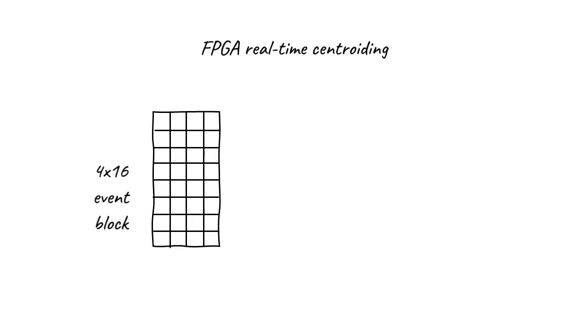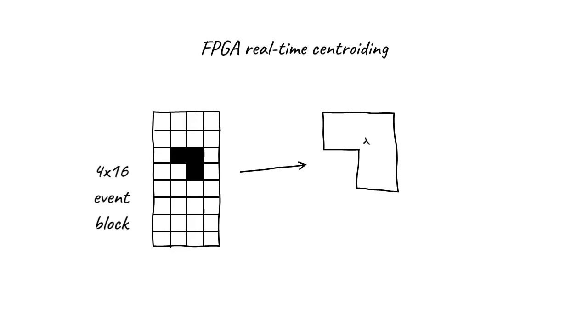When the FPGA receives an event block, it looks for the detection event it contains. A detection event consists of one or more connected pixels. The FPGA calculates the centroid of the detection event with 2x2 super-resolution precision, and records that count on the dose-fractionated movie frame in onboard memory, which will later be output to the computer.